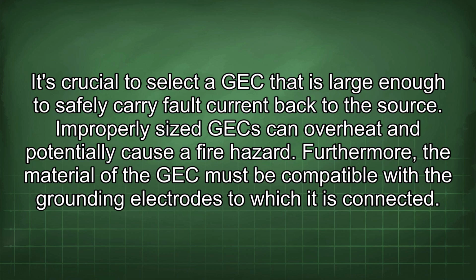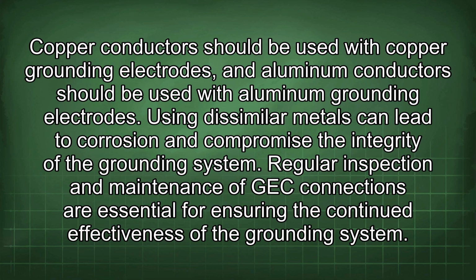Improperly sized GECs can overheat and potentially cause a fire hazard. Furthermore, the material of the GEC must be compatible with the grounding electrodes to which it is connected. Copper conductors should be used with copper grounding electrodes, and aluminum conductors should be used with aluminum grounding electrodes. Using dissimilar metals can lead to corrosion and compromise the integrity of the grounding system.